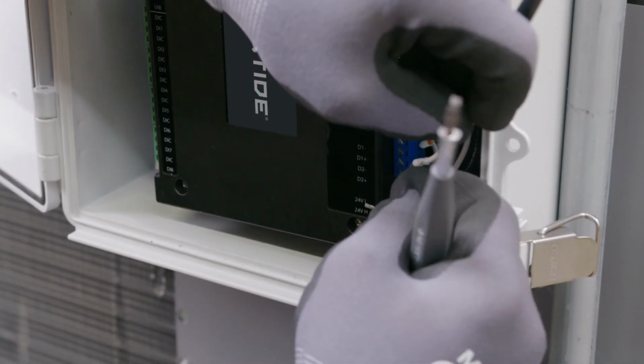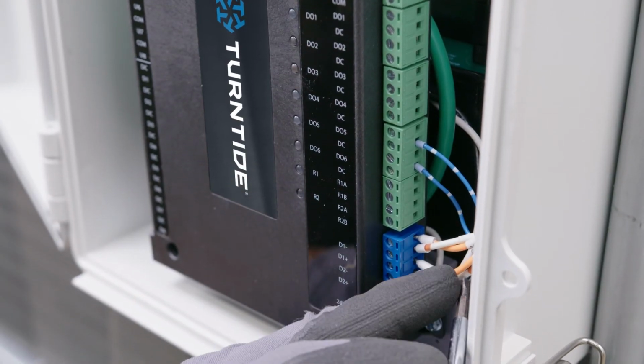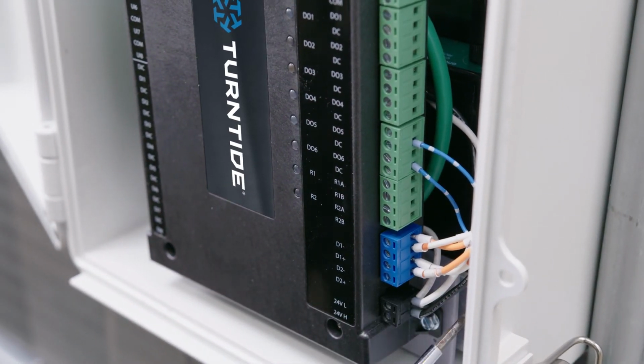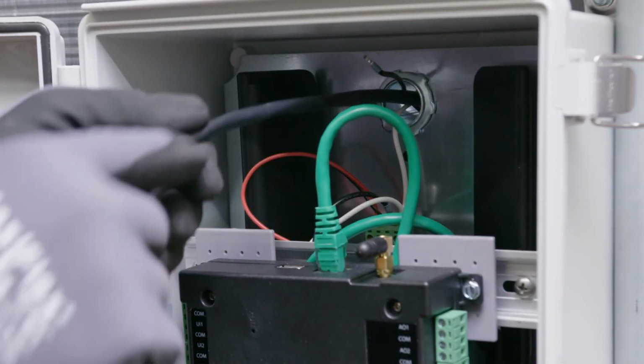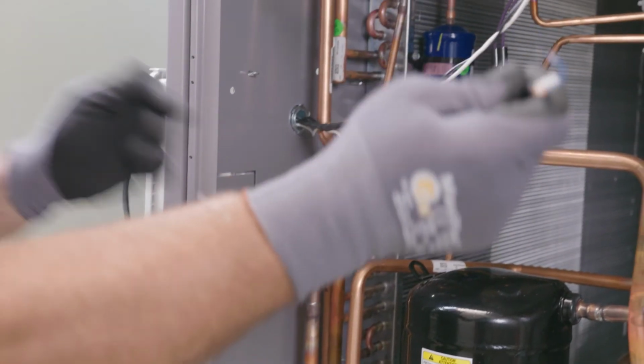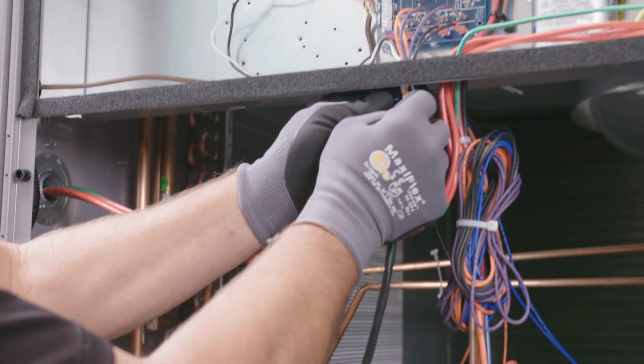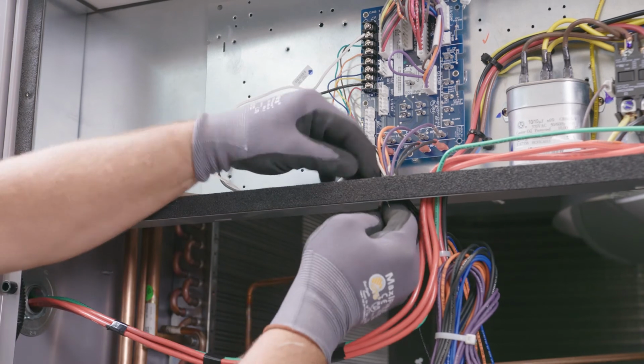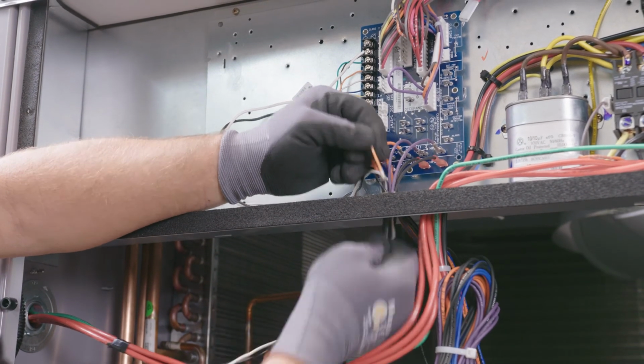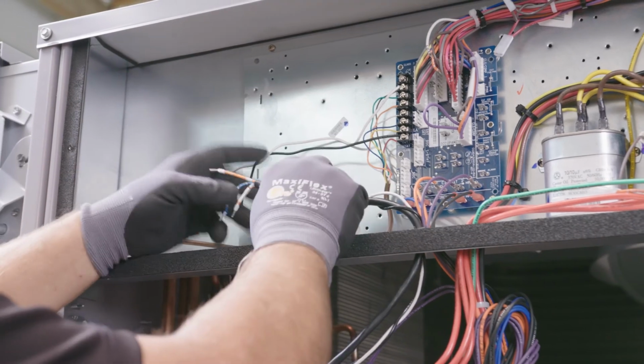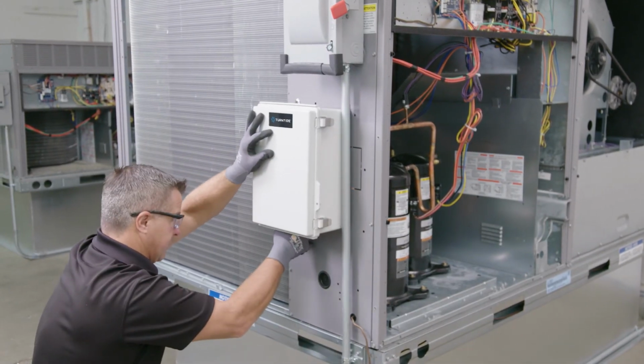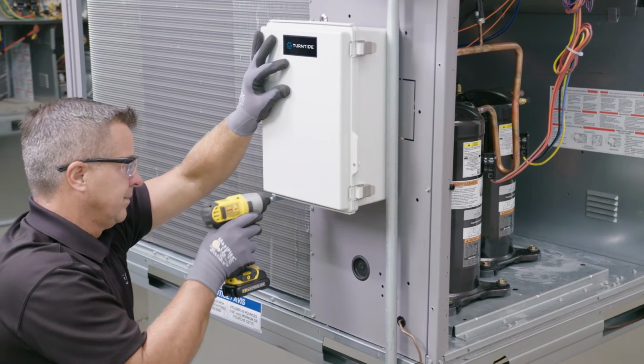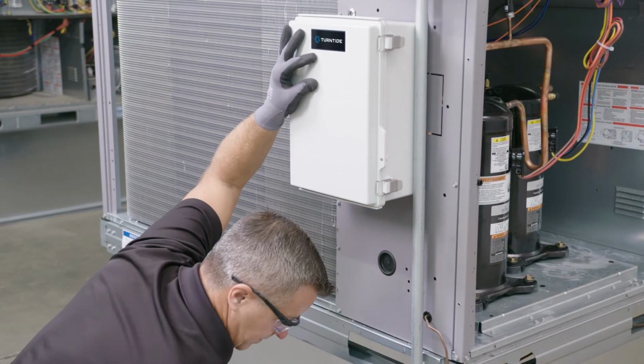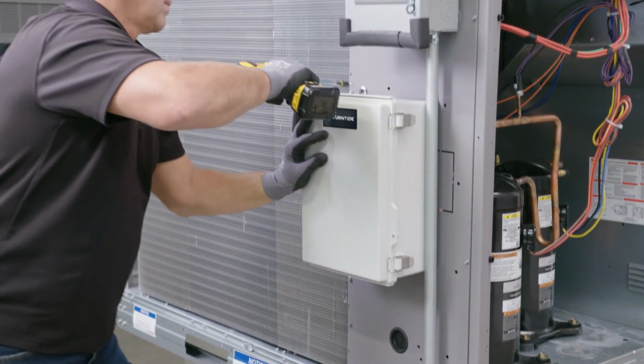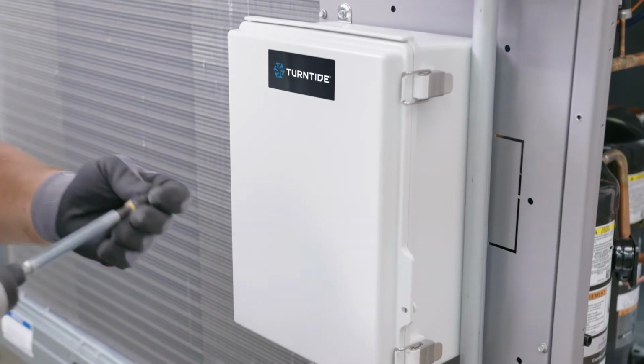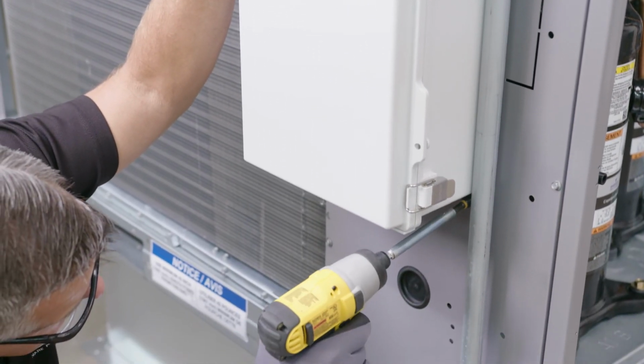In some installations, the supervisor may have been installed during an earlier phase, such as for baseline power measurement. If so, run the Modbus cable between the motor controller and the supervisor. It lands on the D2 positive, D2 negative, and common terminals. Like the motor controller, the supervisor should be installed in a location away from excessive vibration, moisture, electromagnetic interference, and explosive or corrosive vapors. It helps to choose a location that provides easy access to wire the I/O terminals on the controller. If an M&V kit was not installed prior, mount the supervisor using the screws in the 4 corner mounting tabs. Follow standard wiring procedures to connect it to the control panel.